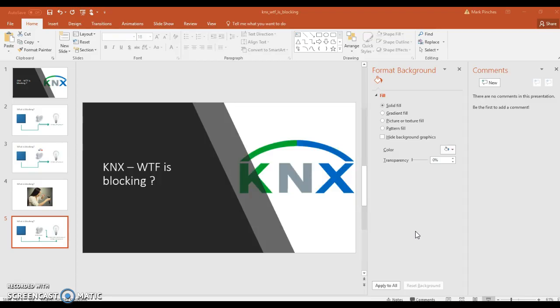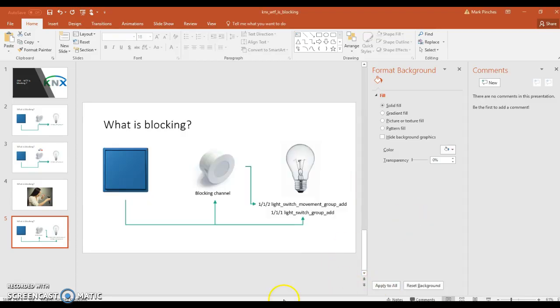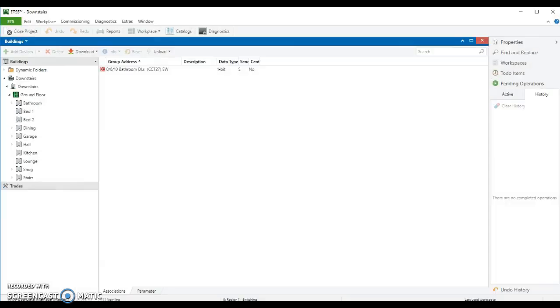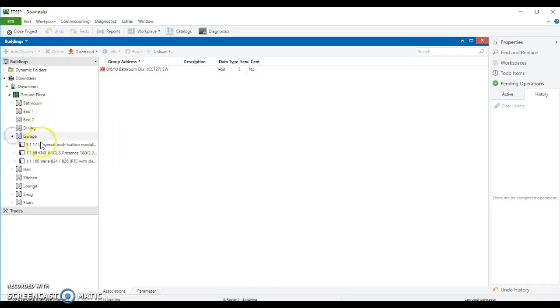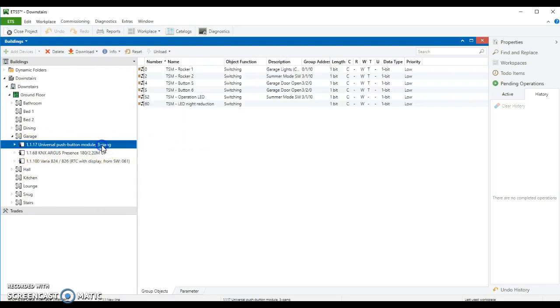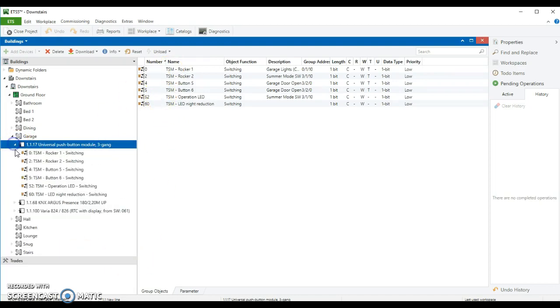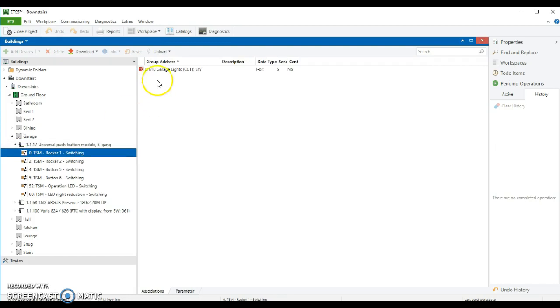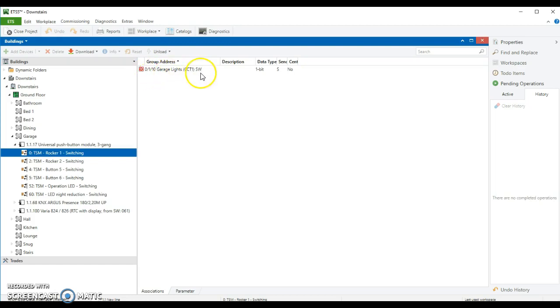So I'll just show you what that looks like on my ETS. So we'll have a look here in the garage where I've got this set up and we've got a push button. And we can see that the push button in this case, if I look at this one, that's the top rocker, this is the light switch. So it's a group address in my case to switch the garage light to 0/1/10. And that will just send an on and an off when that light switch is switched.